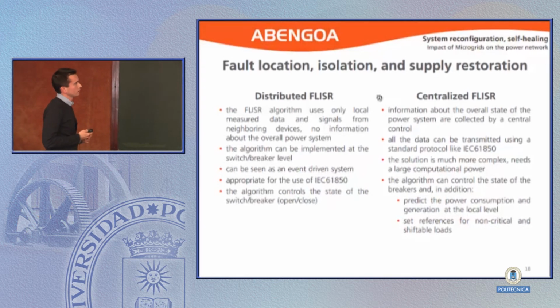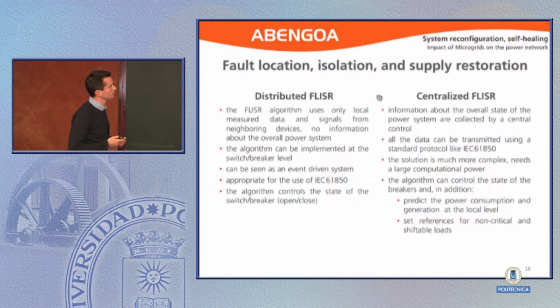A short comparison between the two ways of seeing this algorithm. Very short, in the distributed fault location algorithm, we implement one algorithm on each breaker and feeder, and they will reconfigure the grid online, exchanging messages, especially GOOSE messages from the IEC. And the centralized algorithm reads data from the entire system, runs a complex algorithm, and can reach that global optimum that I was telling you about in the beginning.